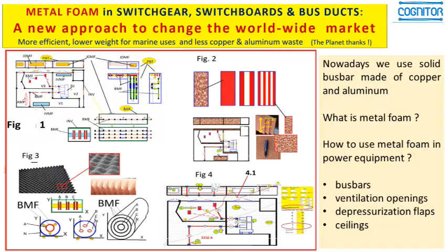The temperature rise is the dominating aspect of any design. Internal arcs, electrodynamical forces, dielectric aspects can all be handled. If we remember the equation, electrical resistance R is equal to the resistivity multiplied by the length divided by the cross-section area. The higher the resistance R, the higher the Joule generation, and the bus bar will heat more.